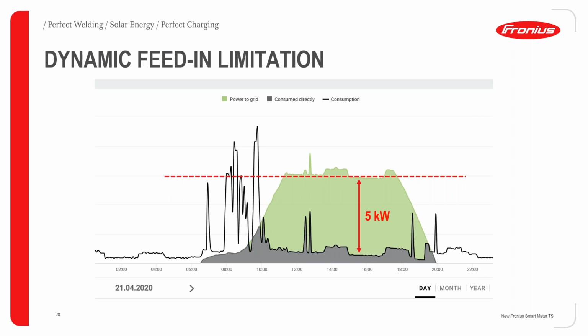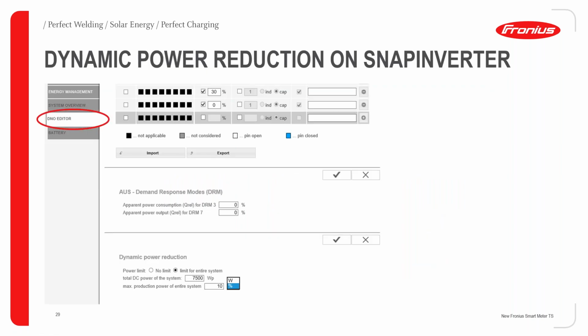So how to set up this value? If you go to the interface page, this is the Snap Inverter series for the data manager cards. If you go to this interface page, you will have an option called DNO editor. Under this DNO editor, you will find dynamic power reduction. Then you can choose the limit for the entire system. Then you have to enter the total DC power of the system. Let's say it's 1000 watt peak, 10,000 watt peak, whatever the watt peak of the panels you are having, or the DC power, that's the total watt peak from the panels, or the inverter output power, you can say there.